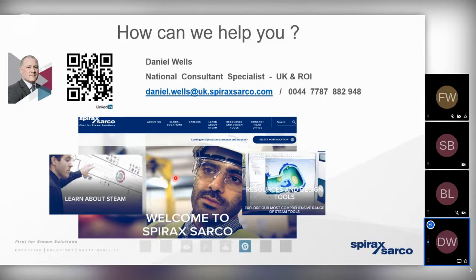So with regards to the dryness value, it really depends upon what we want to know the dryness value for. For example, we could be using steam for direct injection purposes, such as humidification of a hospital operating theatre, or it could well be that we're supplying that steam into a sterilizer of sorts. So typically, we'd want to measure the condition of the steam, and if we're working to BS EN 285 standards that benchmark the steam condition, we're going to want it to be 95% dry or better.